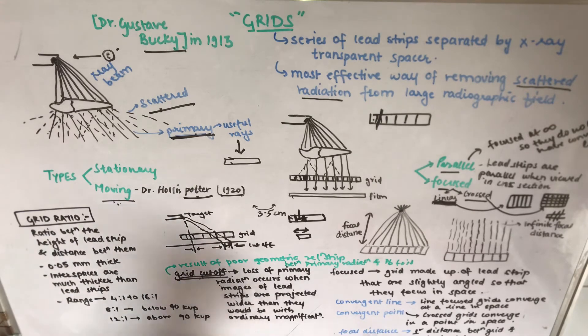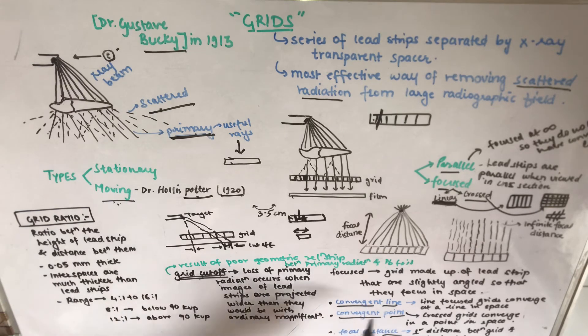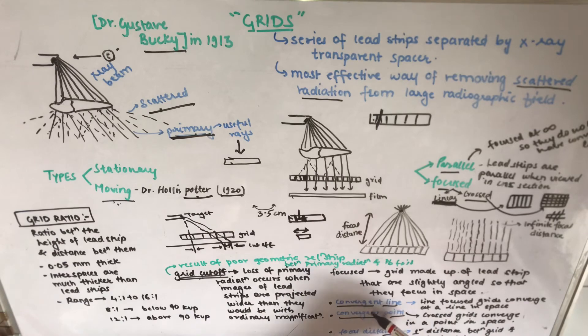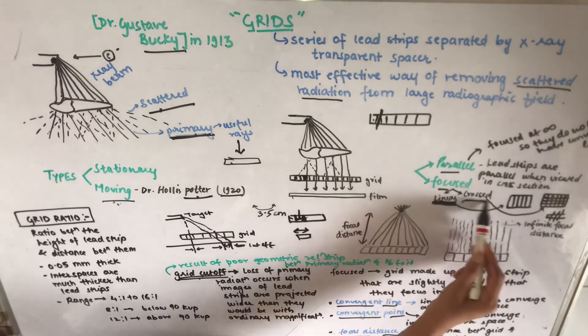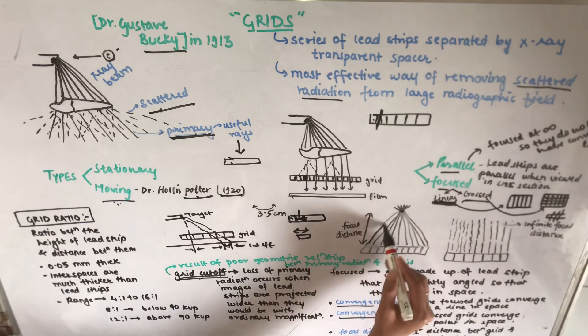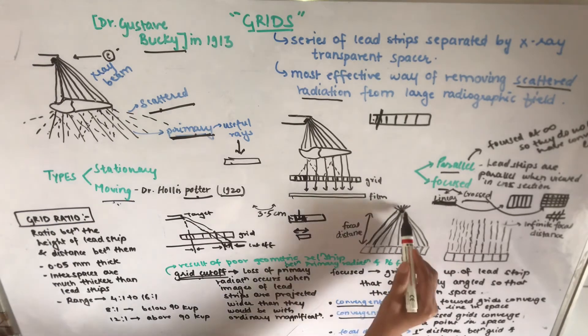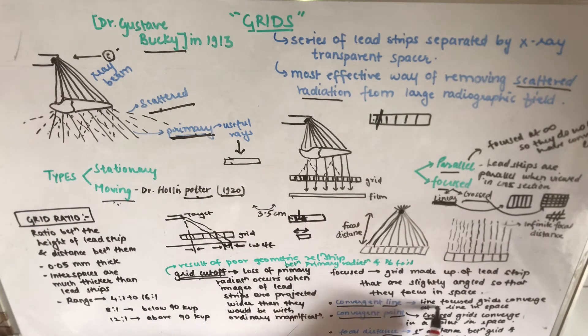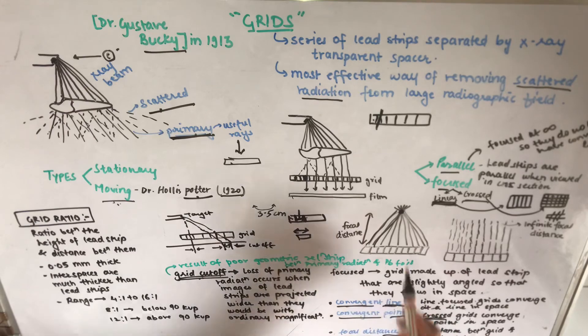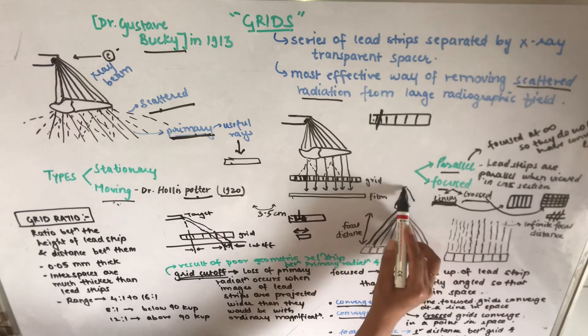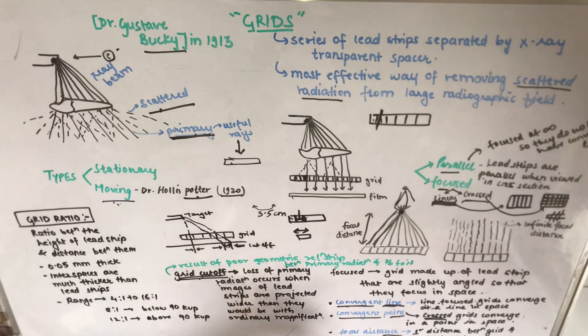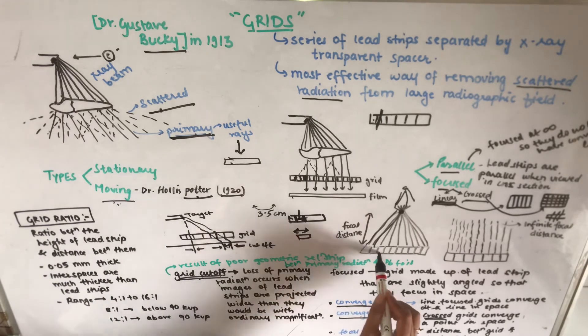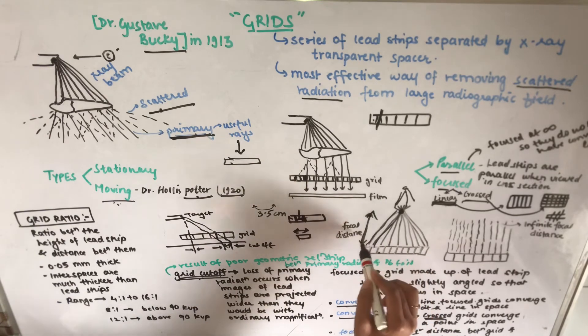There are three related terms: convergent line, convergent point, and focal distance. For linear focused grids, the lead strips converge at a line in space — this is the convergent line. For cross grids, the strips converge at a single point in space — this is the convergent point. The focal distance is the perpendicular distance between the grid and the focal spot or convergent line.